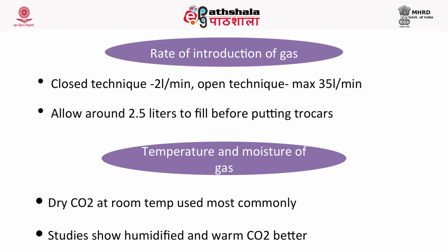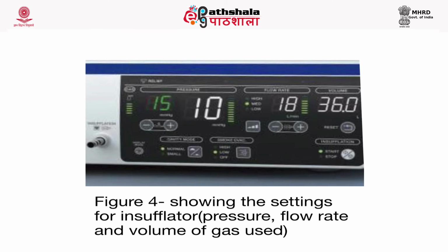Next we have a diagram where we can see the panel of an insufflator. This is a panel which is continuously kept in front of the surgeon's eyes, where he can see the pressure, the inflow rate and the total amount of gas that has been put into the abdominal cavity up till now. These are the monitors present there, and the surgeon continuously monitors these variables.